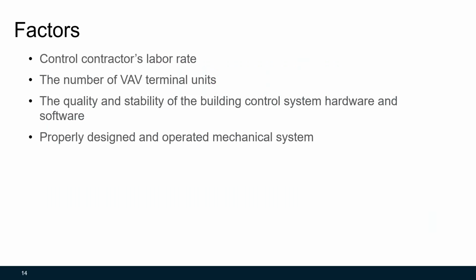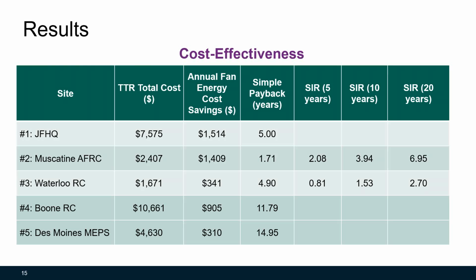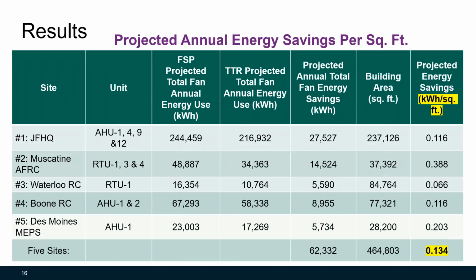Why did the retrofit implementation costs vary so much? The factors include the control contractor's labor rate, the number of VAV terminal units, the quality and stability of the building control system hardware and software, and whether the mechanical system was properly designed and operated. This table shows the cost effectiveness of this control strategy. Among the 5 test sites, the simple payback ranged from 1.7 years to about 15 years. In 3 of the 5 sites, the simple paybacks were less than 5 years. This table shows the projected annual energy savings per square foot. And on average, the fan energy savings is about 0.13 kilowatt hours per square foot.